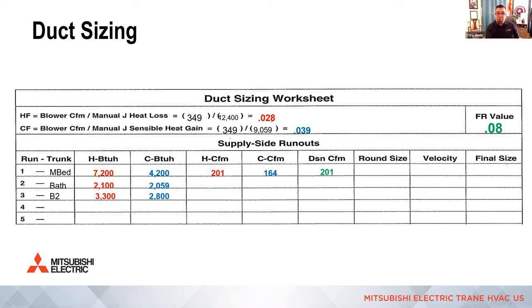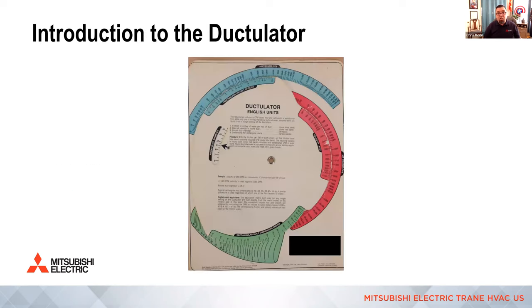We would do the same for the rest of the rooms, right? Now, there's two style duct calculators. If anybody has one, you can follow along. You don't have to. I'm just going to show you some examples. Round duct calculators, pretty simple. There's some key pieces of info you need to look at in order to size runs. And then I'm going to show you velocity, which is the most ignored portion of a duct calculator, and it's really important when it comes to noise and comfort.